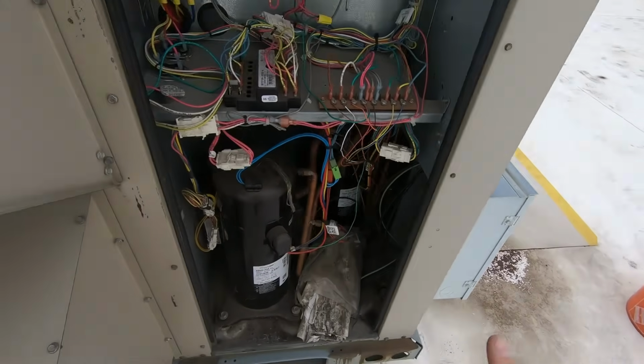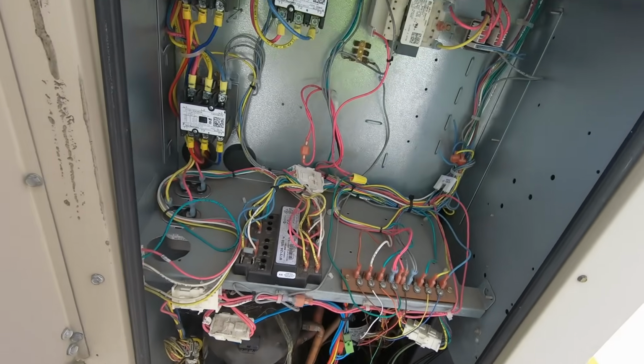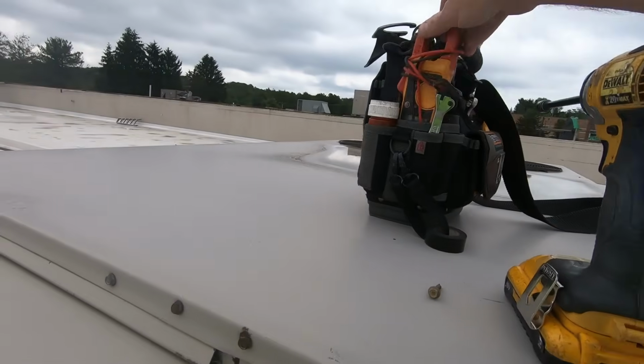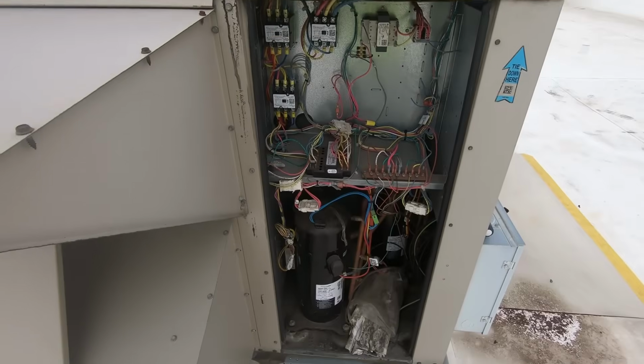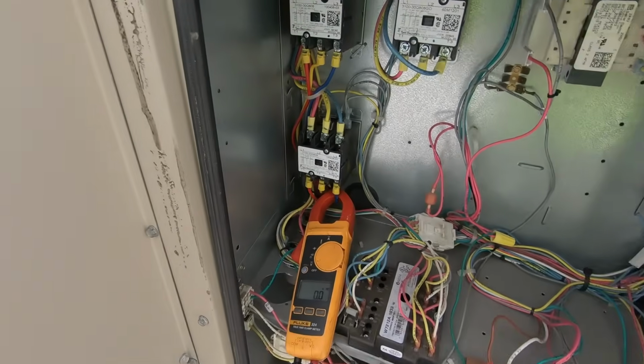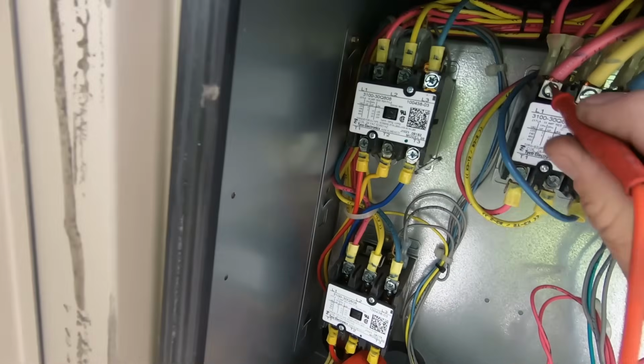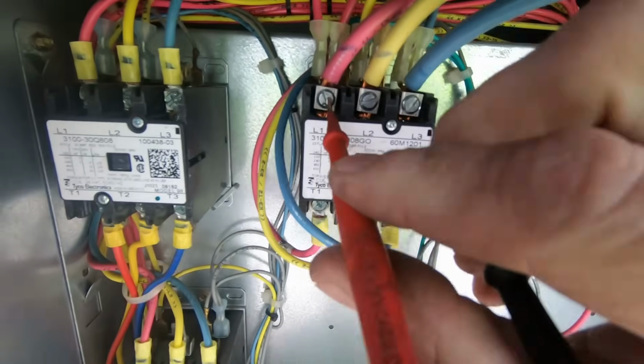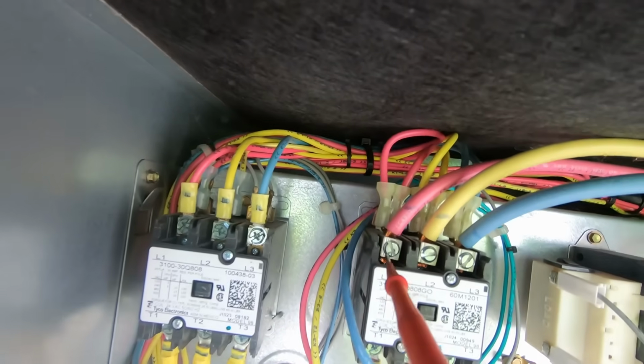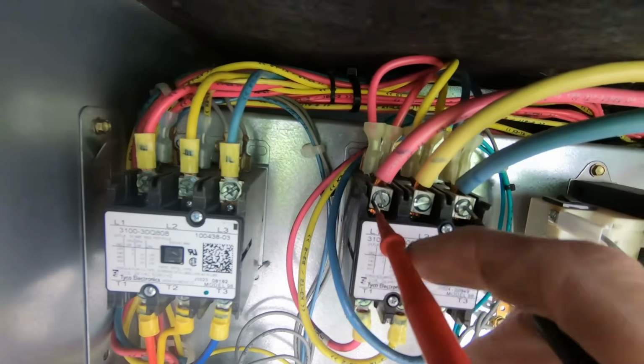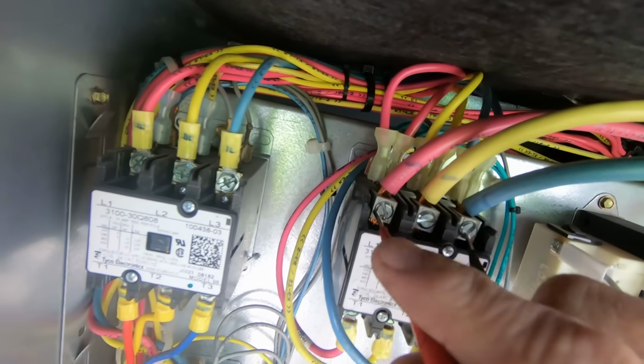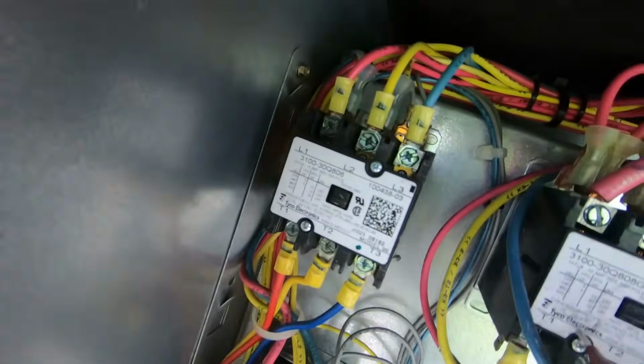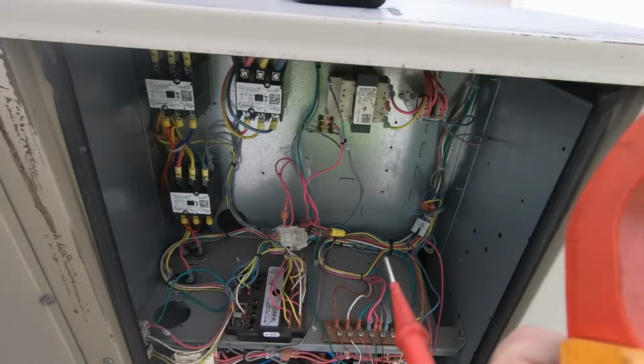They're dirty, you know, there's stuff, but let me see if this thing's even calling. We'll go from there, make sure we have proper voltage. Now this guy has an issue. I have no voltage at the unit. Let's see here if I can do this. Okay. Fuck. 0 volts. Trust me on it. We don't have voltage. Checking. Nothing to ground. Okay, so we have probably a trip breaker or an off breaker.